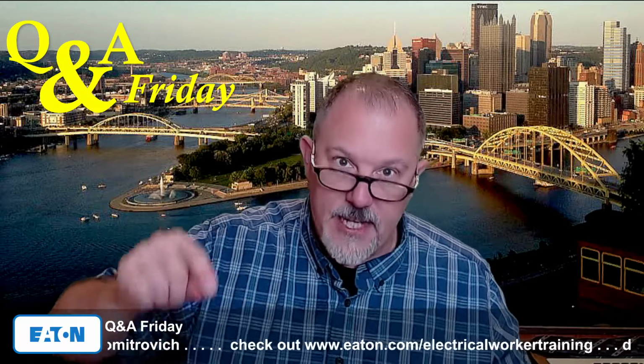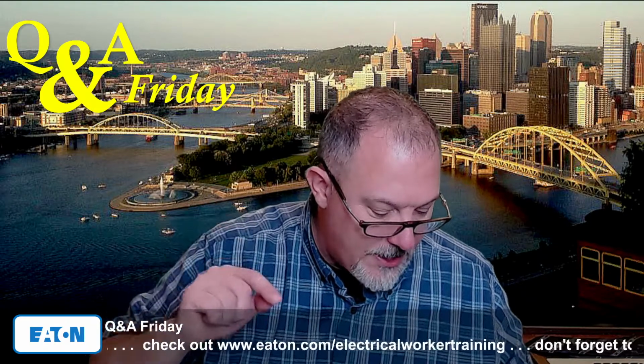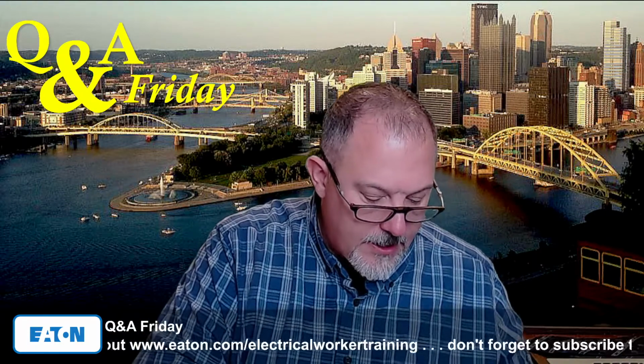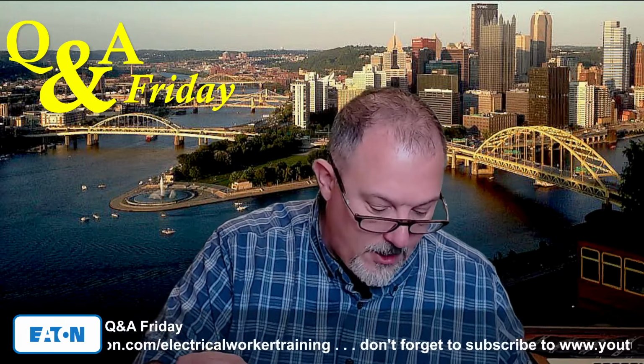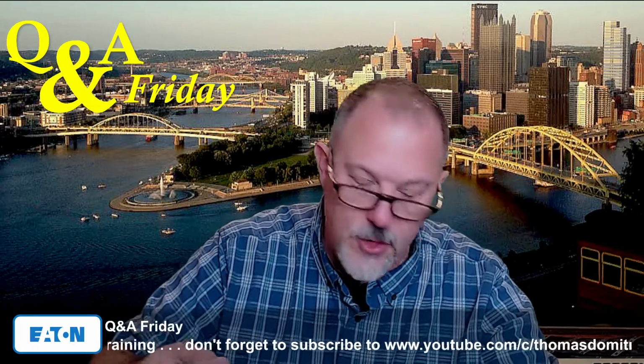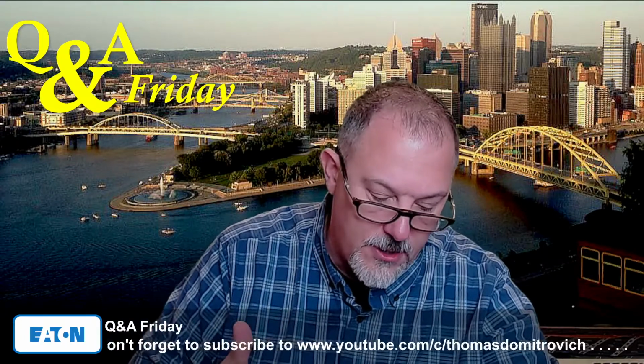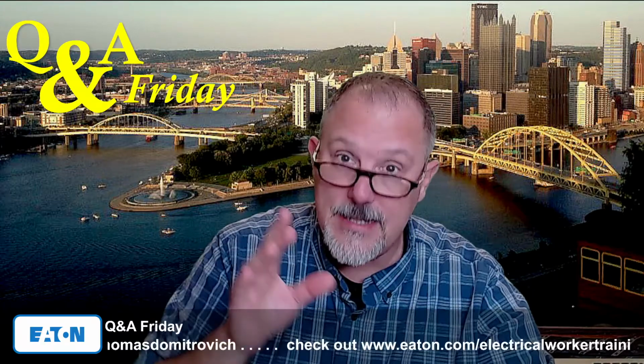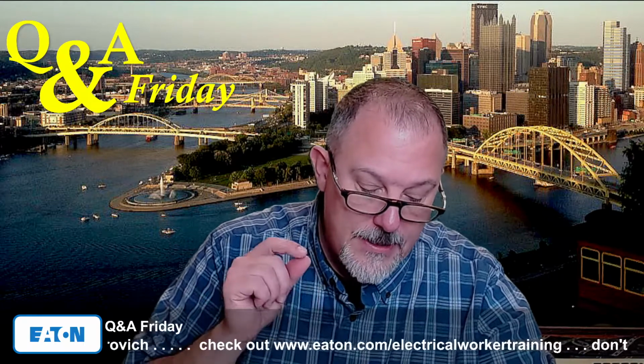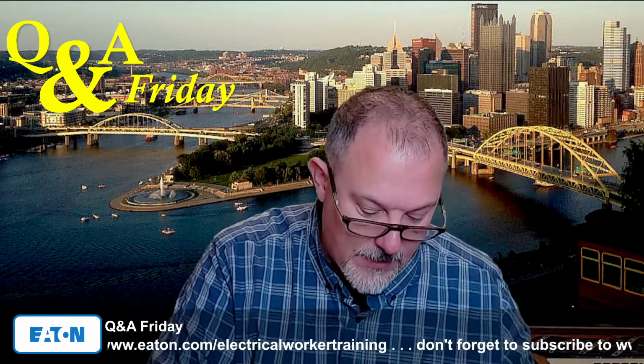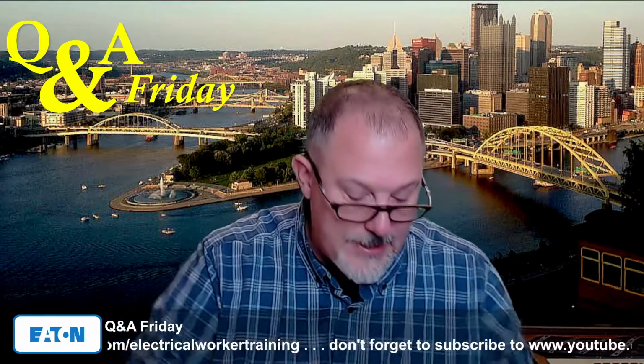110.3, Examination, Identification, Installation, and Use. 110.3(A), in judging equipment, considerations such as the following shall be evaluated: suitability for installation and use in conformity with the code, mechanical strength, wire bending, electrical insulation, heating effects, all these other good things. (B), Installation and Use. Equipment that is listed, labeled, or both shall be installed and used in accordance with any instructions included in the listing and label. (C), Listing. Product testing, evaluation, and listing shall be performed by recognized qualified electrical testing laboratories, etc. Right? That's in 110. So read 110.3.